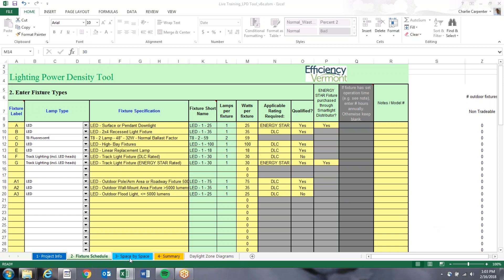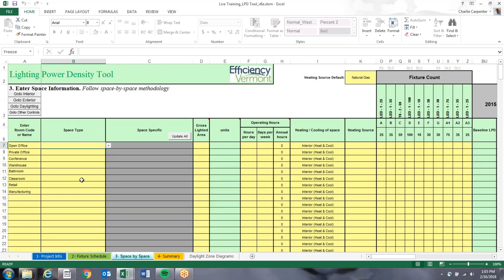Now moving on to the third tab, the Space by Space tab, where we input each interior and exterior space individually. You cannot combine spaces — putting all your offices or bathrooms together will affect the controls calculation. You need to break up each space individually. The tool looks at the area and space type to determine what controls are required.